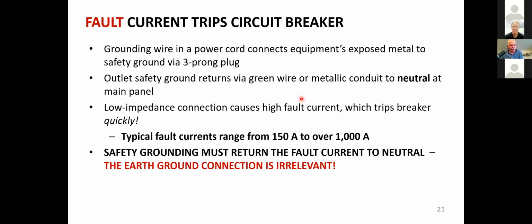But anyway, if the green wire is in place, then the current doesn't go through anybody's body. It flows through the green wire back to the neutral connection at the breaker panel. So it's an alternate pathway for the current on the live conductor to get back to the grounded conductor, the white wire or the neutral. And if this connection is low enough impedance, the fault current gets very high. A typical fault current runs from 150 to 1,000 amperes, and it largely depends on how much wire is between the breaker panel and the outlet.